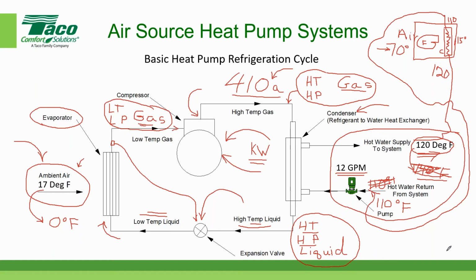So extreme conditions, like -15 degrees, not a good application, right? Well, each manufacturer rates their heat pumps for heating capacity. Because it's a heat pump, by the way, it's reversible. I'm going to show some diagrams of that. So they are specifically designed for certain outdoor or ambient temperatures, and they have different strategies. In other words, you'd have to have a fairly large compressor. The lower the ambient temperature for the same supply water temperature, the more work the compressor has to do. So there's a trade-off between how big and how efficient the compressor is.